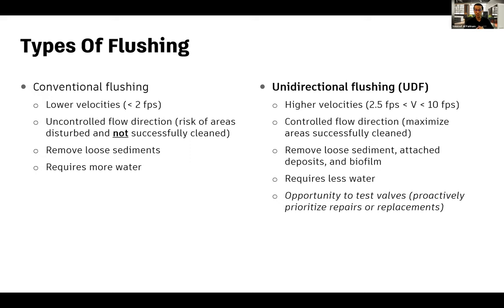Another comparison: conventional flushing can only remove loose sediment, whereas UDF can remove loose sediment, attached deposits, and biofilm — because you're able to hit the shear stresses from maximizing velocities. Research also shows UDF requires less water. Finally, UDF allows you to proactively test valves and hydrants, which can go into prioritizing repairs or replacement schedules.